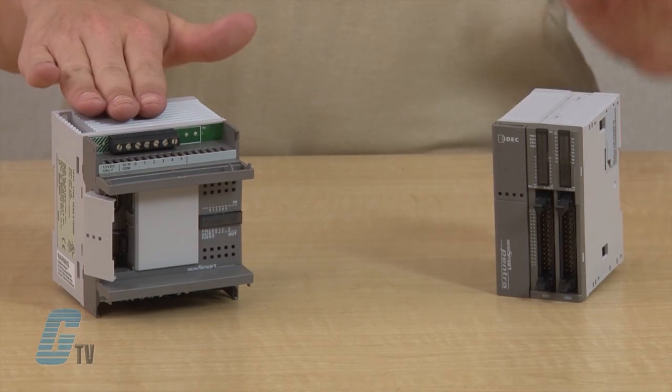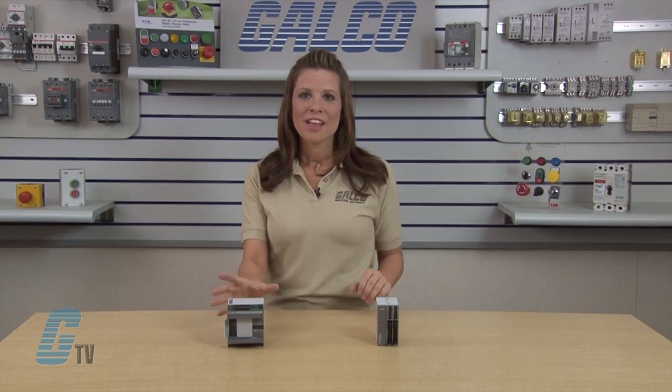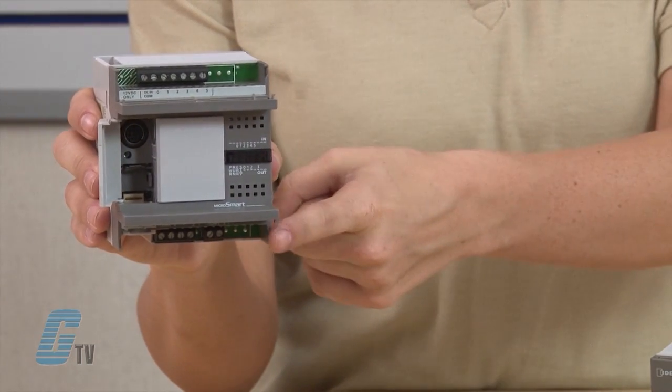The IDEC MicroSmart Pentra is a family of micro-programmable logic controllers available in two styles of CPU modules: all-in-one and slim types. The all-in-one type CPU module has 10, 16, or 24 input-output (I/O) terminals and is equipped with a built-in universal power supply to operate on 100 to 240 volts AC or 24 volts DC, using four 16-point I/O modules.